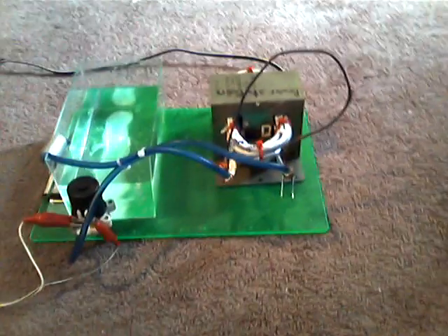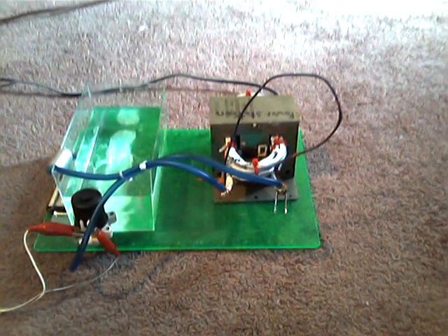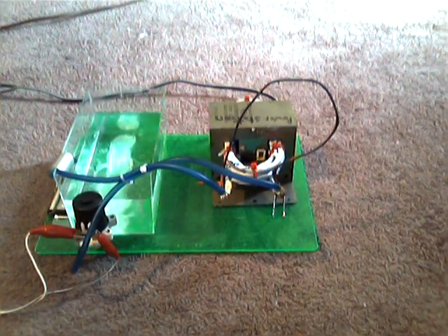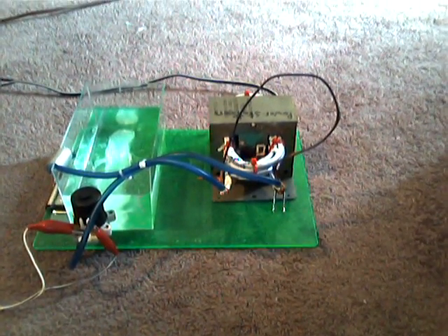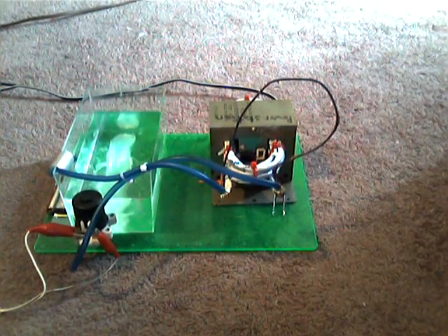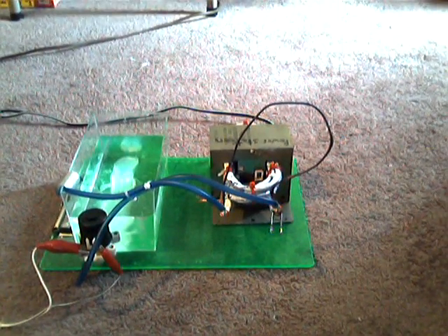Okay, here's the unit I'm shunt testing. It's an eight-turn transformer, and I'm getting 8.45 volts out of this. The last test I did was at 320 amps peak, fluctuating significantly for whatever reason.